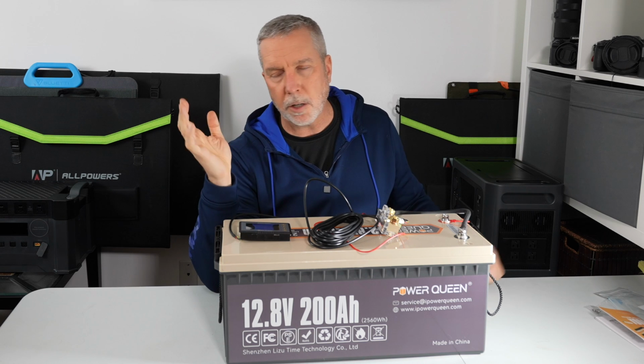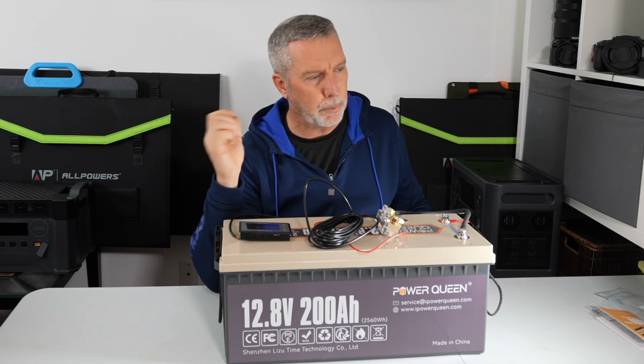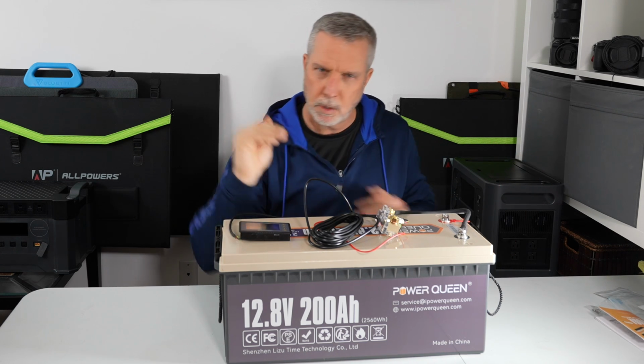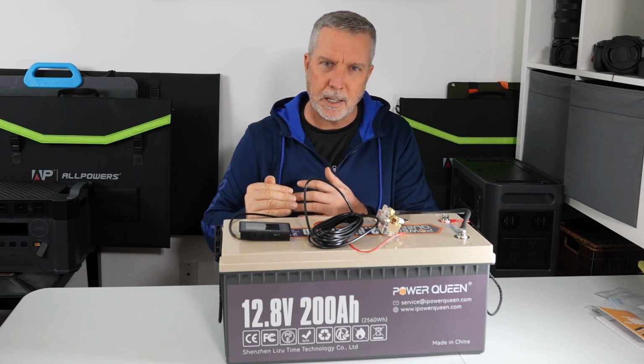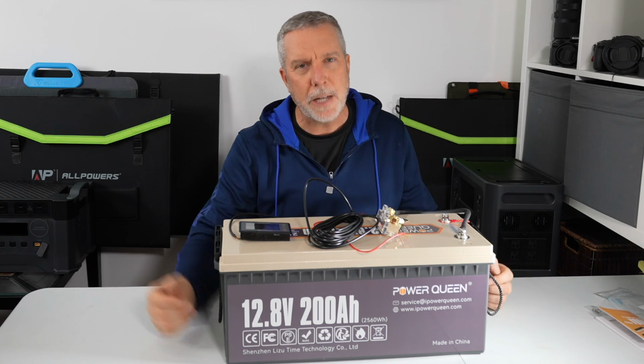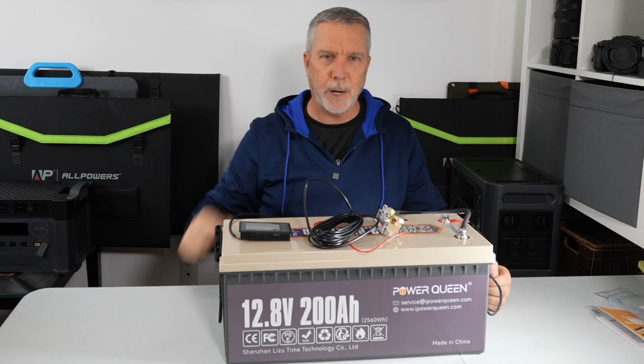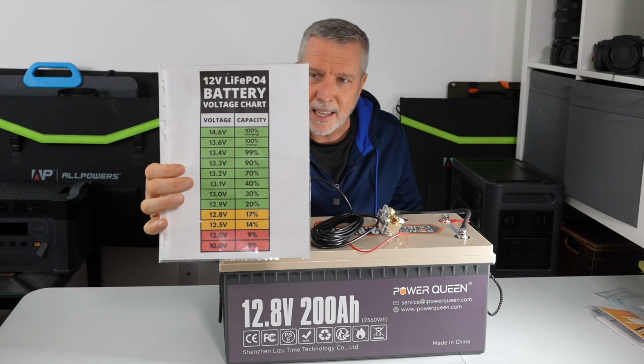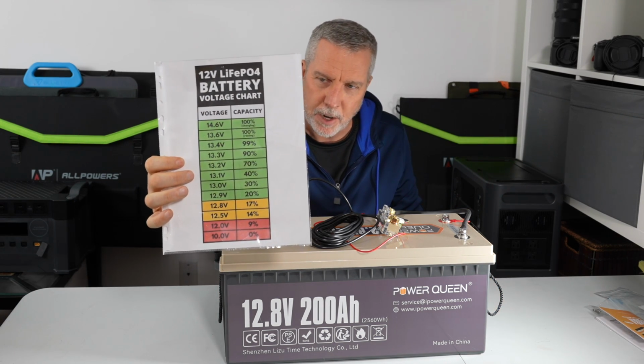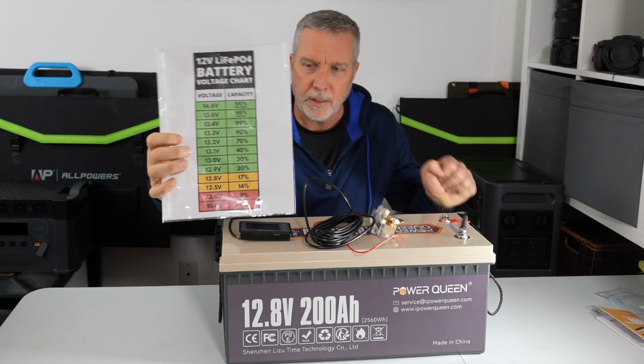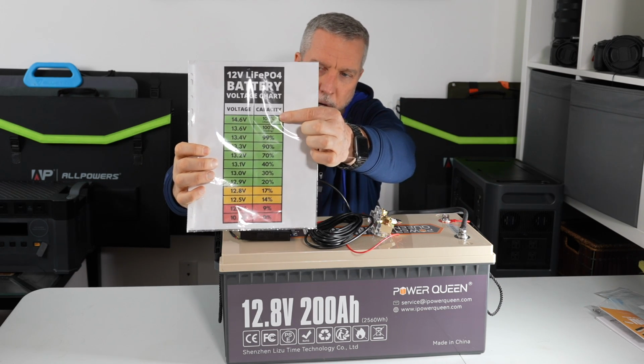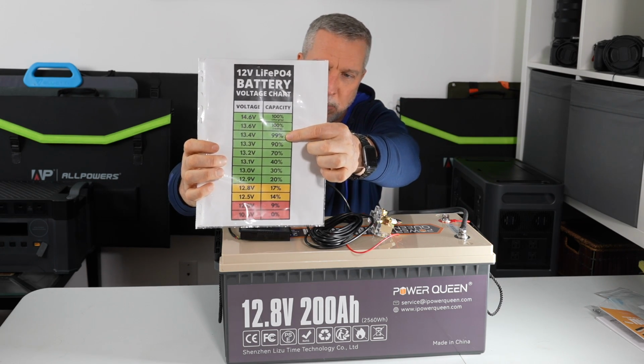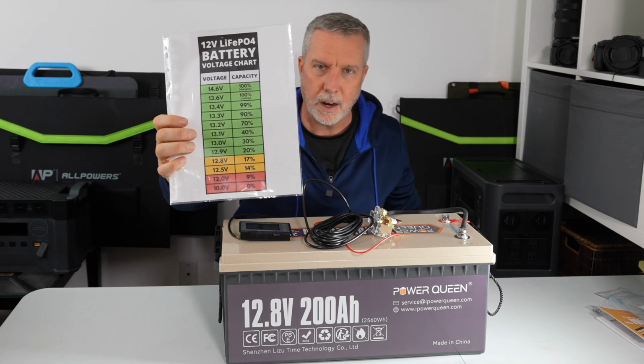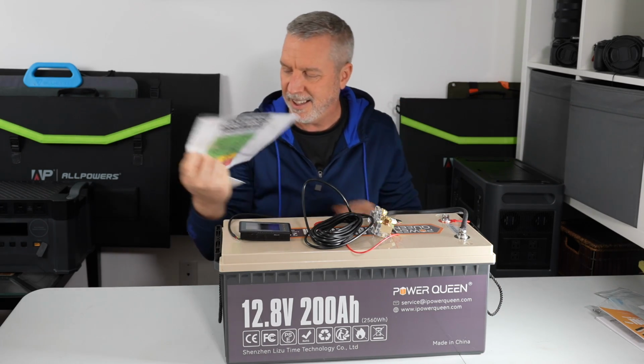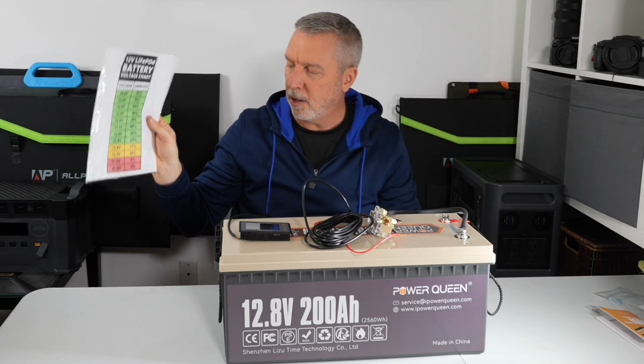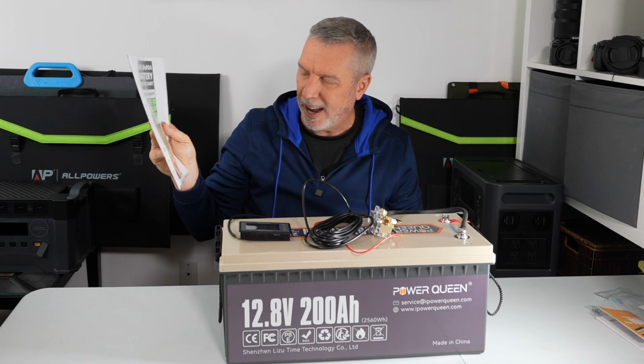So if my house bank batteries are at 12.6 volts or something, I'm like, okay, is that closer to full or closer to empty? You can pull up a sheet — I'll bring it over right now — that shows what a typical lithium iron phosphate battery should read in voltage when it's being charged and still on the charger at 100%, when it's resting at 100%, and then down to what's pretty much dead. In the red is dead.